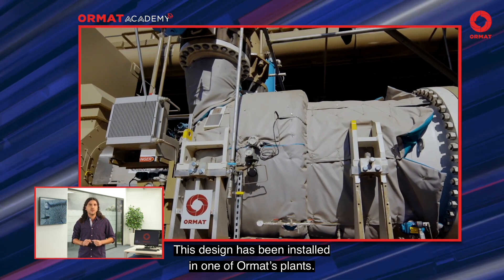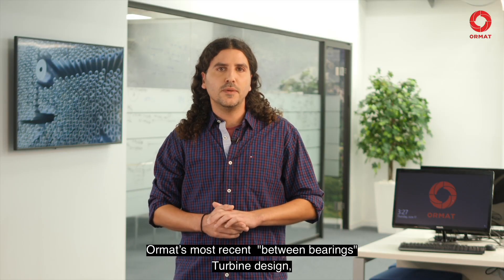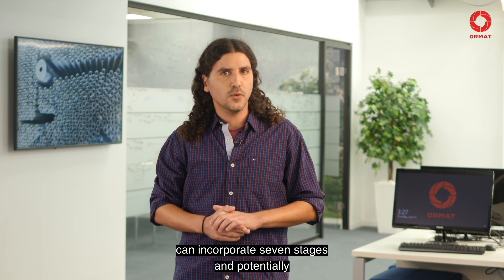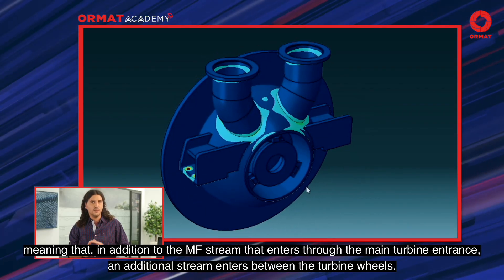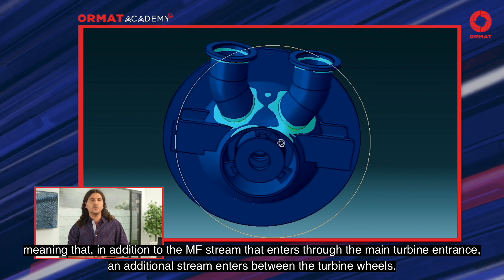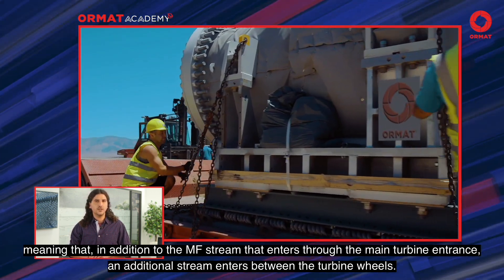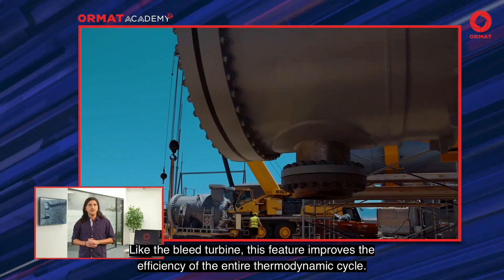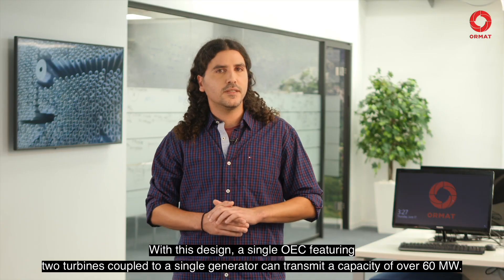This design has been installed in one of Ormat's plants. Ormat's most recent Between-Bearing Turbine design can incorporate seven stages and even potentially more if necessary. It can also incorporate an interstage injection, dual pressure, meaning that in addition to the motive fluid stream that enters through the main turbine entrance, an additional stream enters between the turbine wheels. Like the bleed turbine, this feature improves the efficiency of the entire thermodynamic cycle.